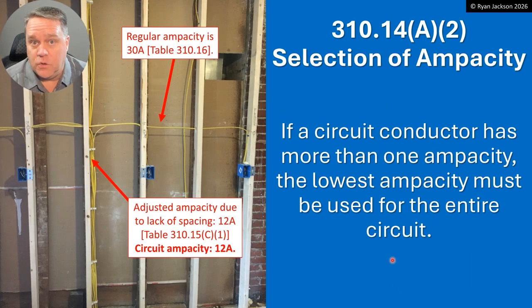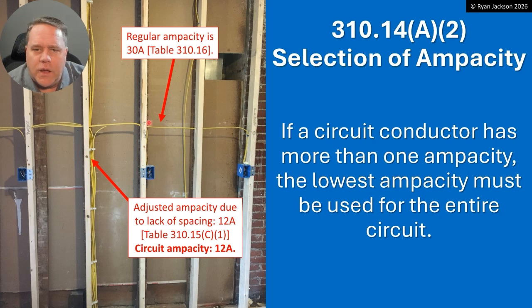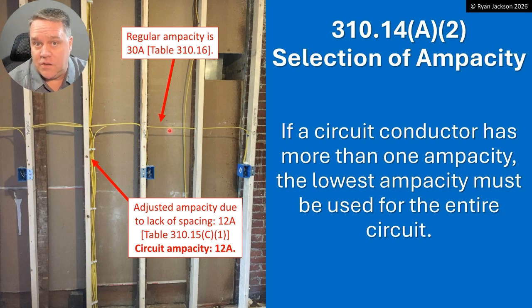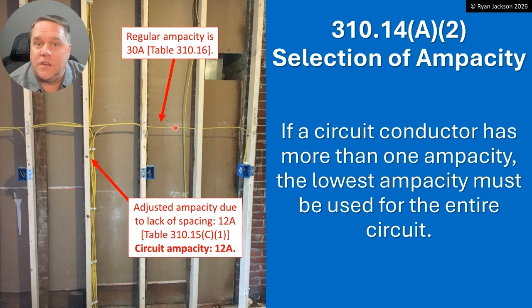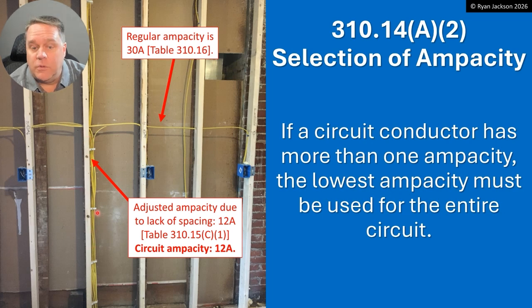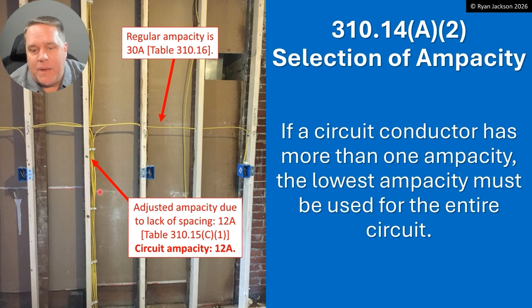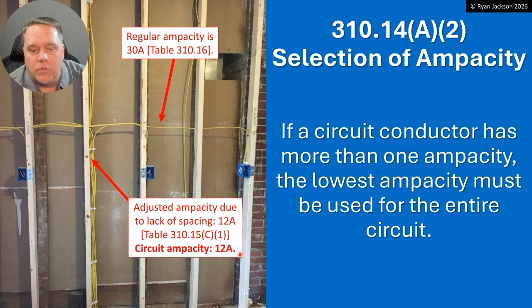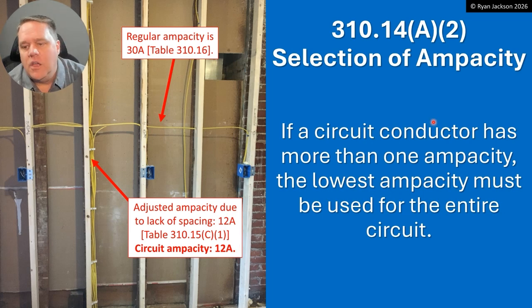How can a conductor have more than one ampacity? The answer is different conditions of use in a single circuit. Take 12-gauge NM cable: straight from Table 310.16, at 78–86°F ambient with no more than three current-carrying conductors, you get the standard ampacity. But then look what happens under a different condition of use — when a whole bunch of cables are bundled together without maintaining spacing. That lack of spacing reduces the ampacity down to 12 amps after the adjustment in 310.15(C)(1). So we have one wire with two different ampacities: 30 amps and 12 amps.